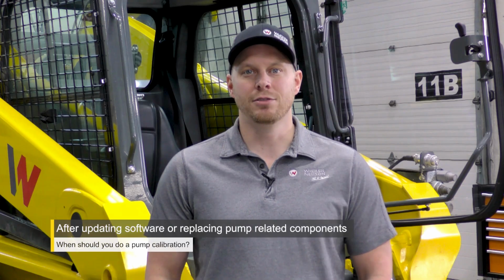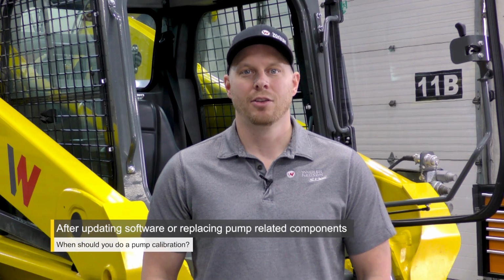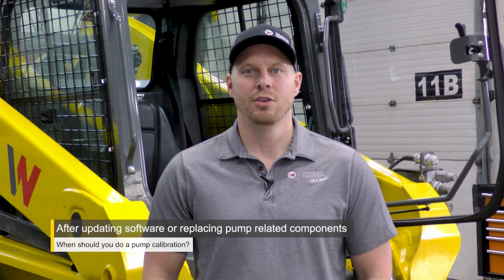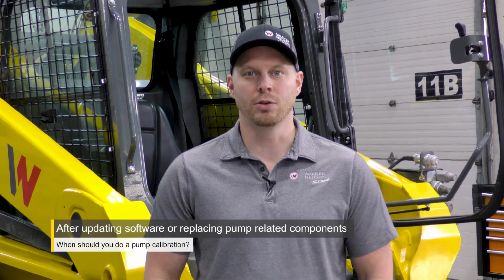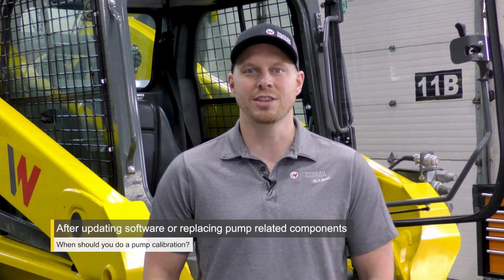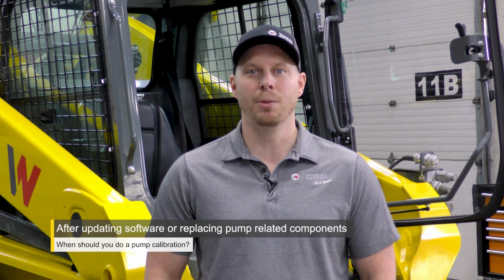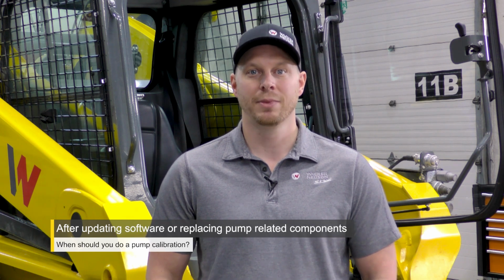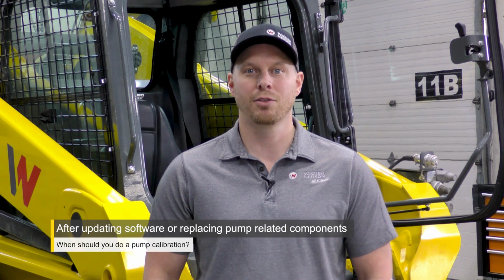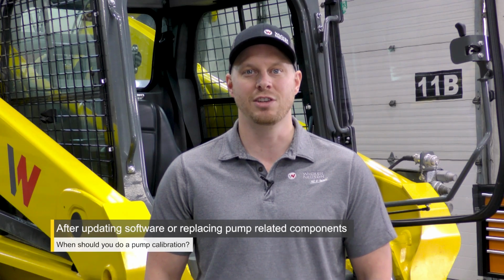So what would prompt you to do a pump calibration? There's a couple reasons why. First, you have flash programmed and updated software to the machine, to the drive controller and the machine controller. The second reason is you've replaced any pump related components. Could be the pump, could be the drive solenoids, or the drive controller. These are the reasons why you would go through the pump calibration procedure.